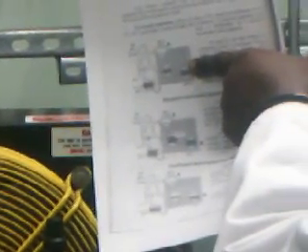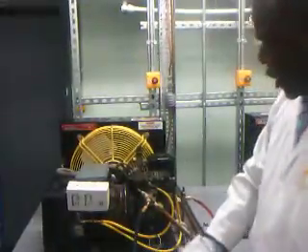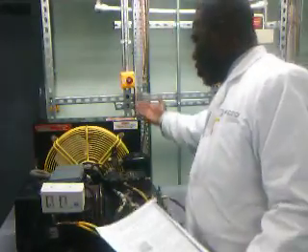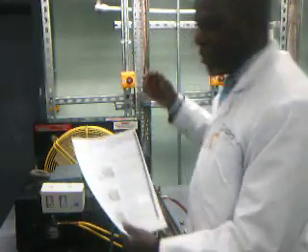So that 39, you take a temperature at the outlet of the condenser. It's somewhat close to the bottom pipes, but again, at the outlet of the condenser, take a temperature from there. So for instance, we are getting a condensing temperature of 39. Now that condensing temperature of 39 is what we are recording on the high side gauge. That is what you have towards the bottom of the condenser, or towards the last pipes of the condenser.